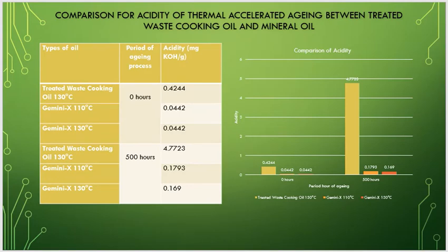For comparison of acidity, treated waste cooking oil at 0 hour is 0.4244, and at 500 hours is 4.7723. And for mineral oil at 110 degrees Celsius at 0 hour is 0.0442, the same as mineral oil at 130 degrees Celsius, 0.0442 mg KOH per gram. And at 500 hours, mineral oil at 110 degrees Celsius is 0.1793, and for mineral oil at 130 degrees Celsius at 500 hours is 0.169.